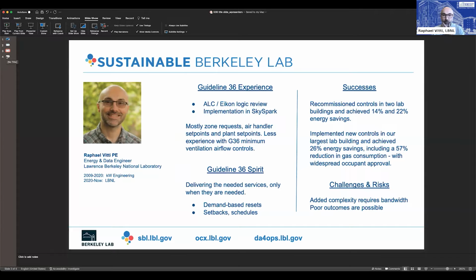I added this little blurb about the spirit of Guideline 36, because Chris and I, in preparing for this, realized that we hadn't actually looked at the document in a very long time. For me, Guideline 36 meant trim and respond for air handling unit duct static pressure set points and supply temperature set points. But there's, of course, a lot more to it.